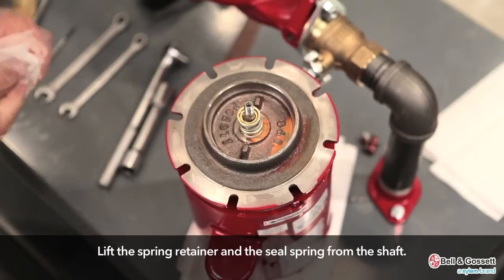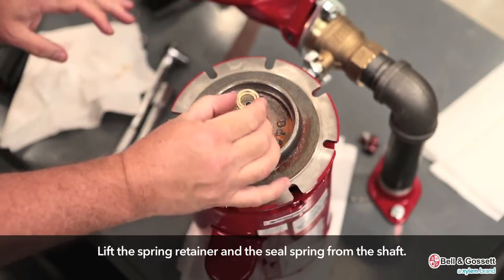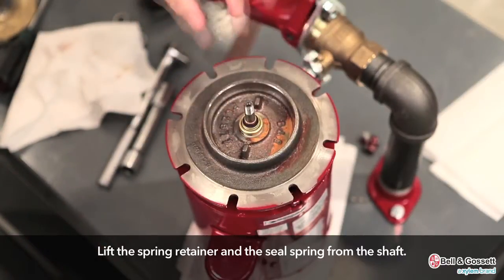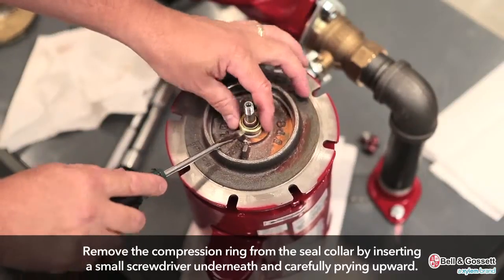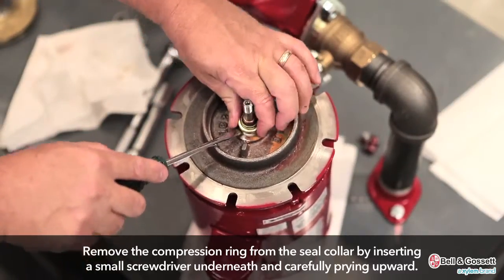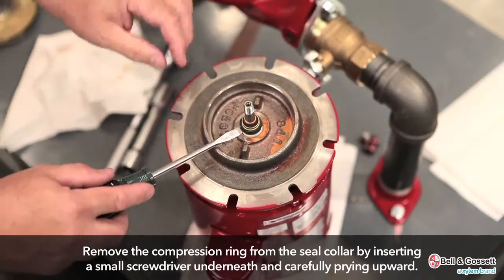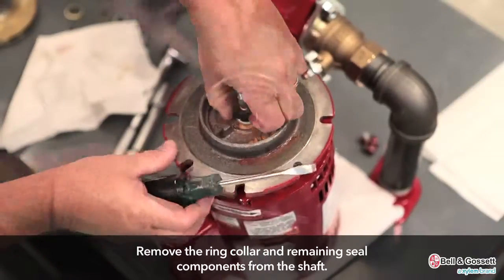For all except the 1.25 inch or 3.18 centimeter seal assembly, lift the spring retainer and the seal spring from the shaft. Remove the compression ring from the seal collar by inserting a small screwdriver underneath the ring and carefully applying an upward force. Remove the ring collar and remaining seal components from the shaft.